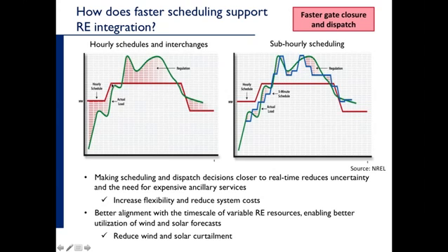Now, during that hour, I don't have access to the dispatch stack, but I do have access to units that can provide regulation. And different parts of the world do regulation in different ways. In some areas, you have automatic generation control. In other areas, you have manual control, which might be based on frequency deviations. It doesn't matter how you do that, but the fact is that you have to move some generation outside of the economic dispatch process, and you can see that here in green.